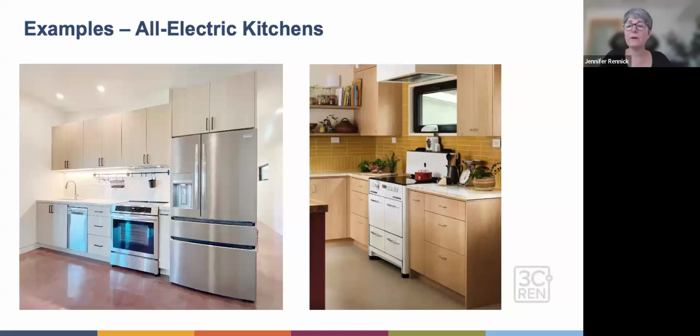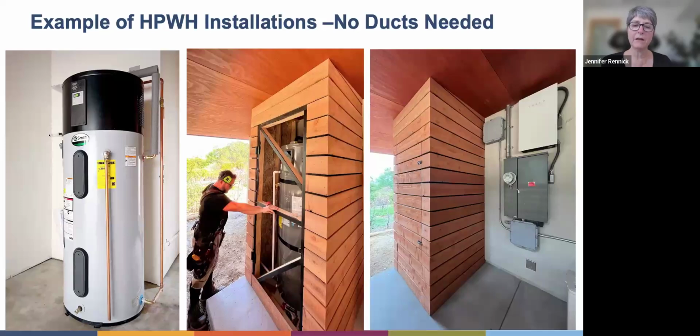outside. Oh, before you go on, I just want to point out, Mike, that heat pump water heaters are becoming so common now. And we, like the California Energy Commission, are expecting a lot more of these to be installed. Just a heads up, in the 2025 energy code coming up, there are more explicit mandatory requirements on that ventilation and the condensate and all of that, because that's maybe a pain point, to make sure that the units get plenty of outside air or plenty of volume of air in the garage or house, so they can extract the heat from it efficiently. So be on the lookout for that, especially with our other trainings coming up. We'll be addressing the code changes.